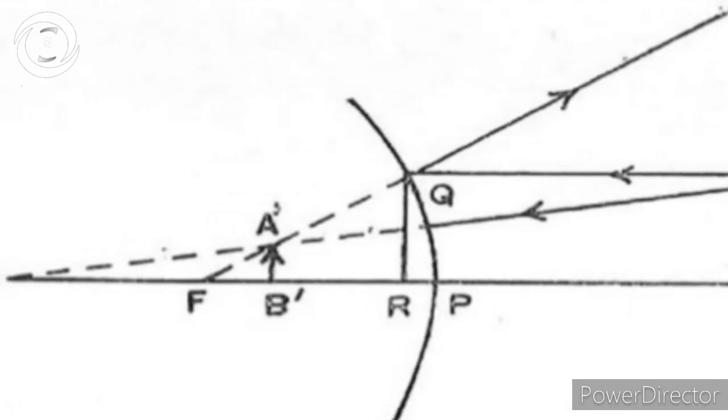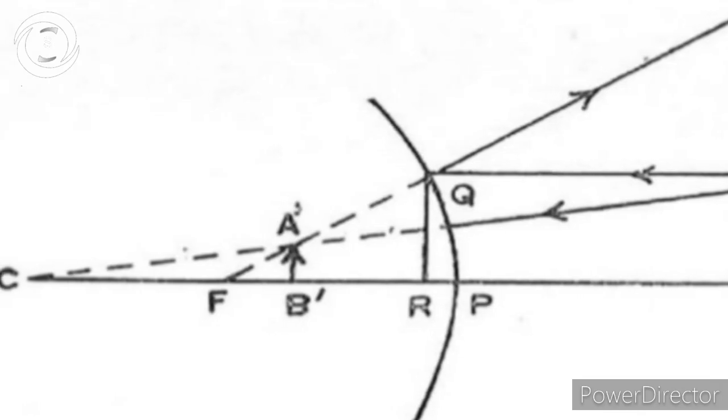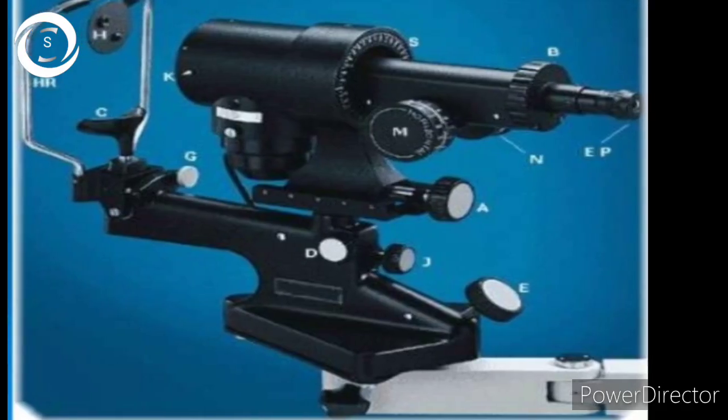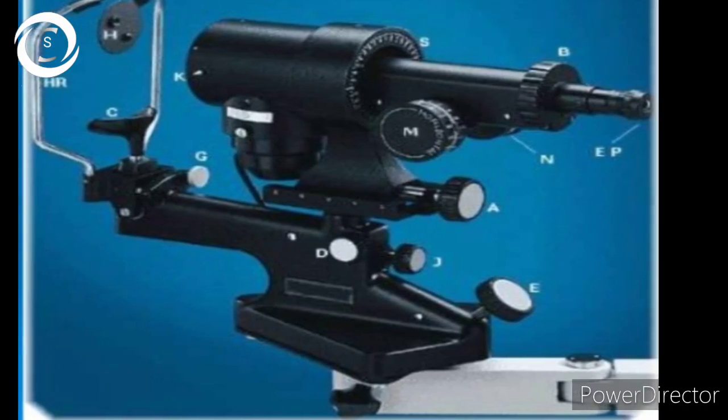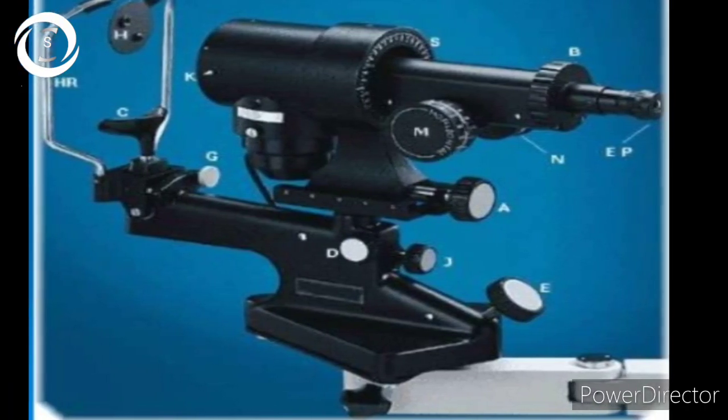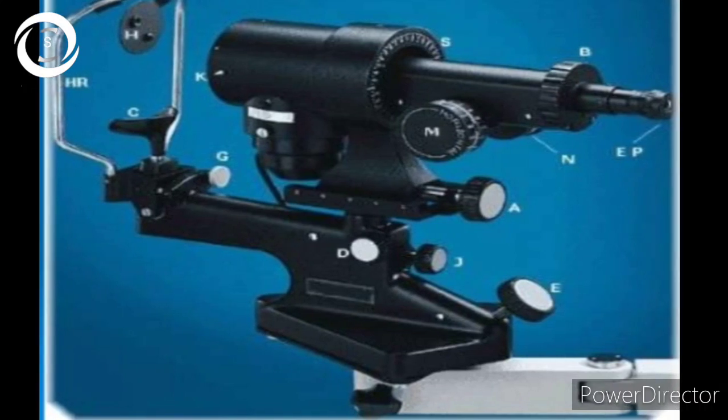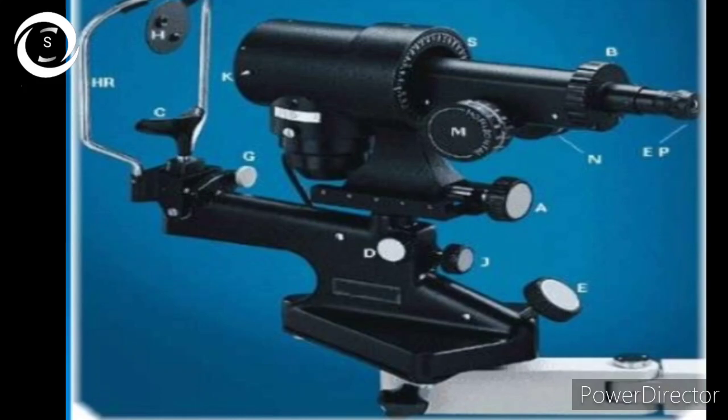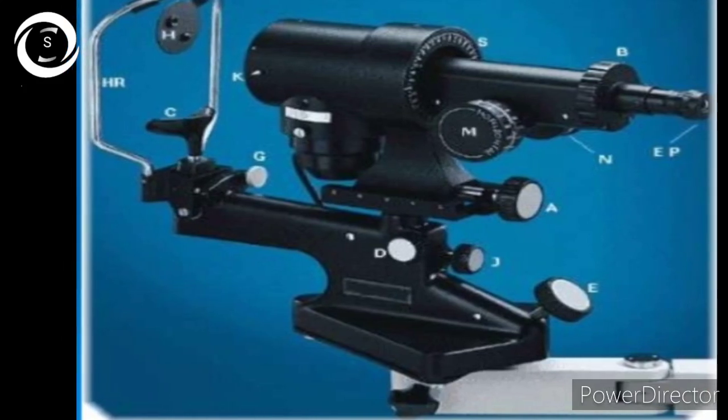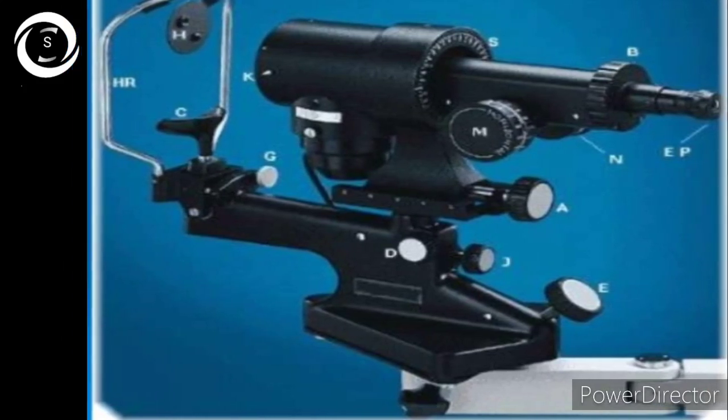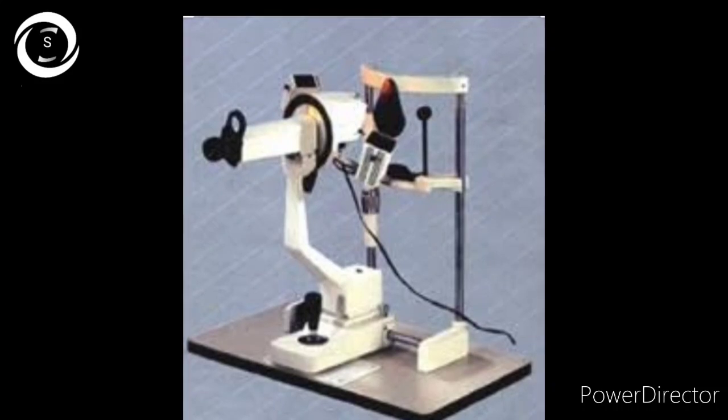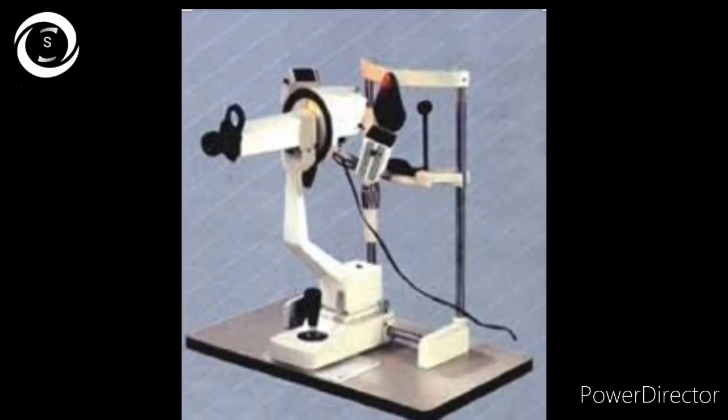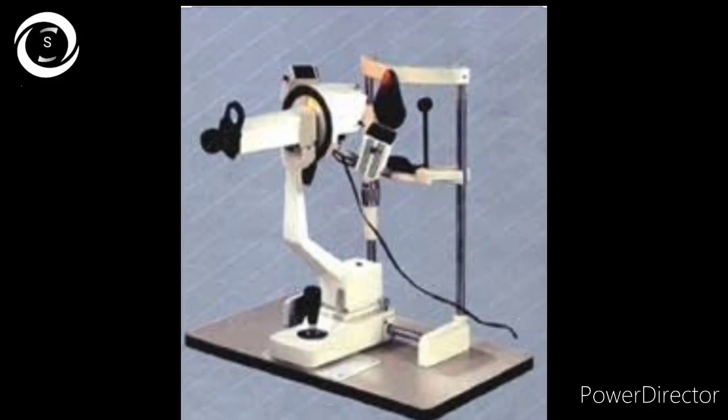Keratometers are based upon two concepts of doubling. Fixed object size with variable image size is called variable doubling and occurs in Bausch and Lomb keratometer. In Javal-Schiotz keratometer, you have fixed image size with variable object size.